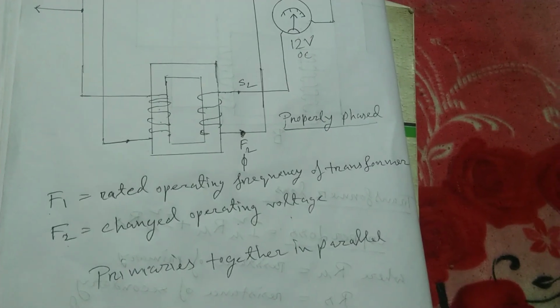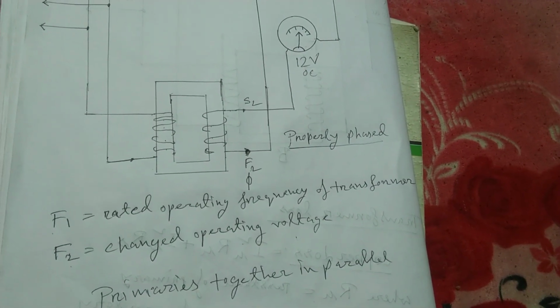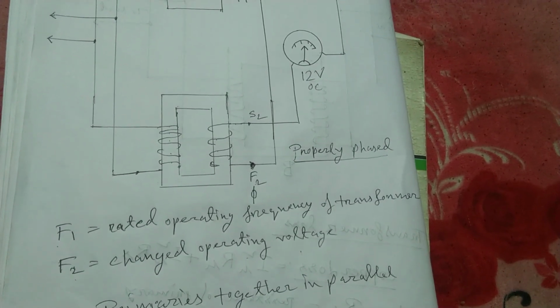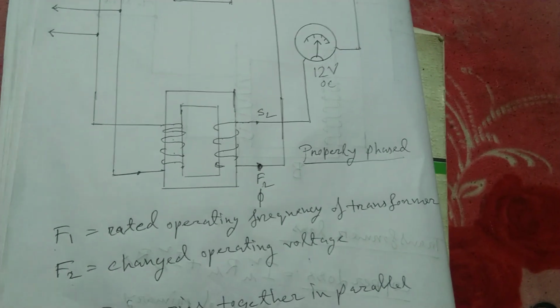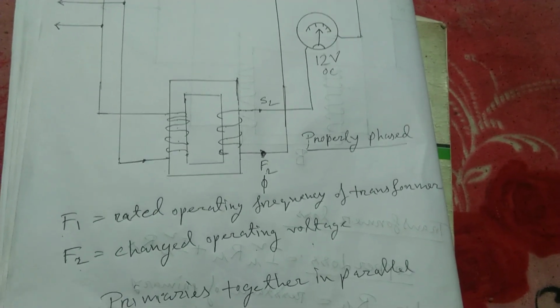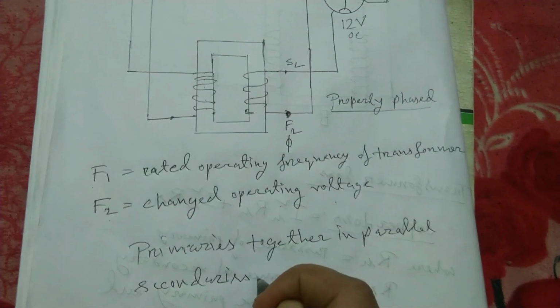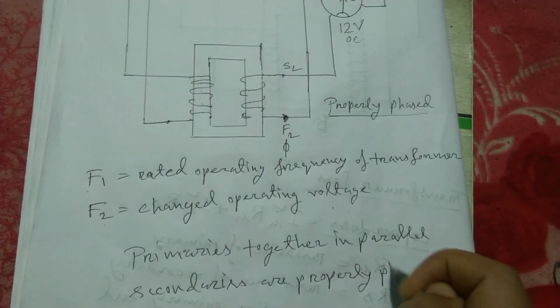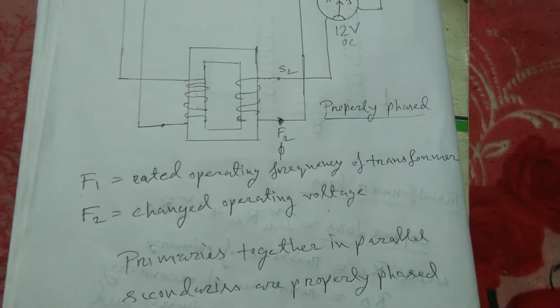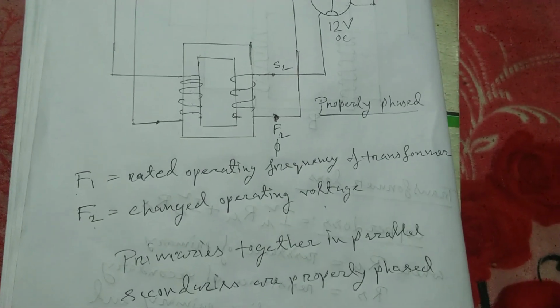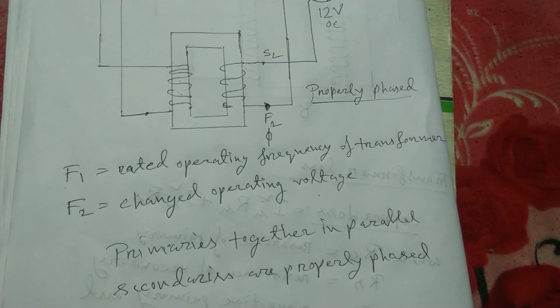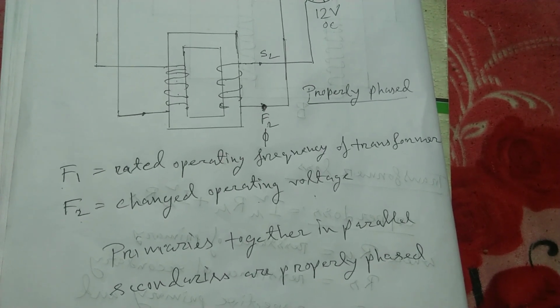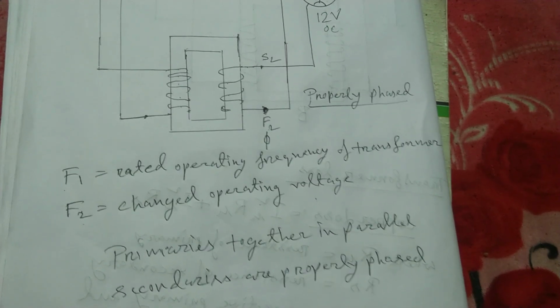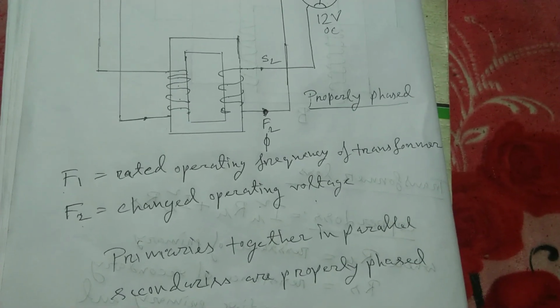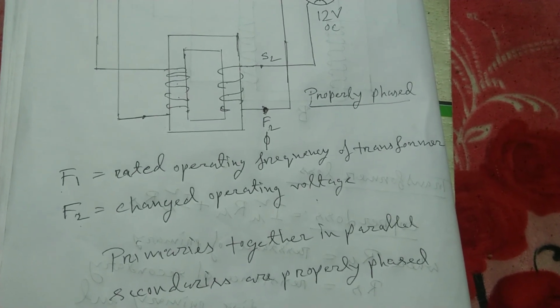Now, if the secondaries are properly phased, the meter will indicate the sum of the secondary voltages. If the meter indicates the difference of the secondary voltages, the connection to one of the secondaries may be reversed. One of the primary windings may be reversed.